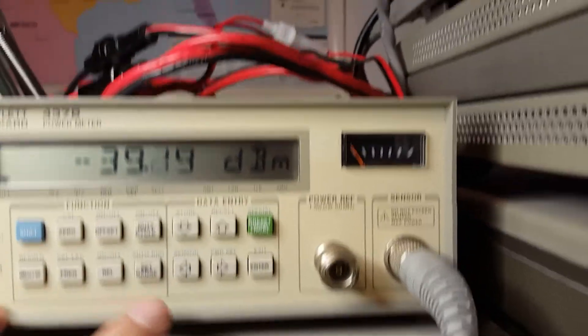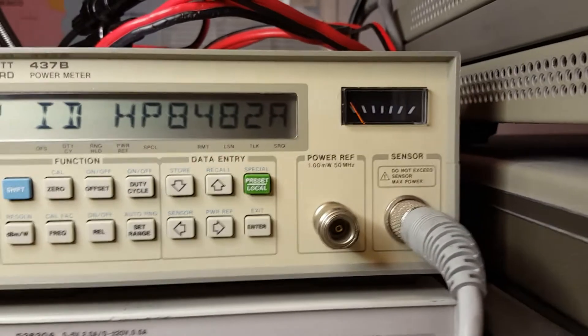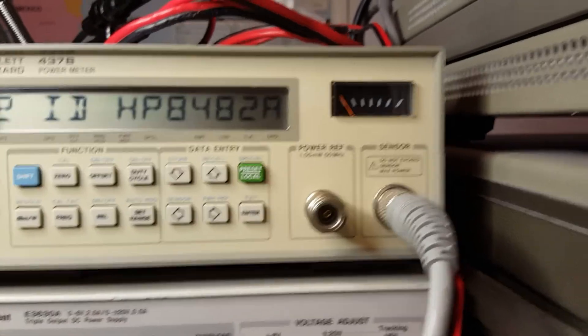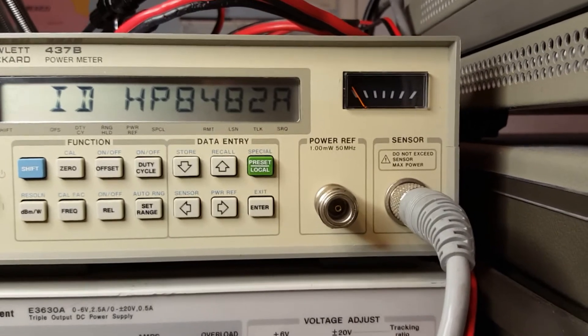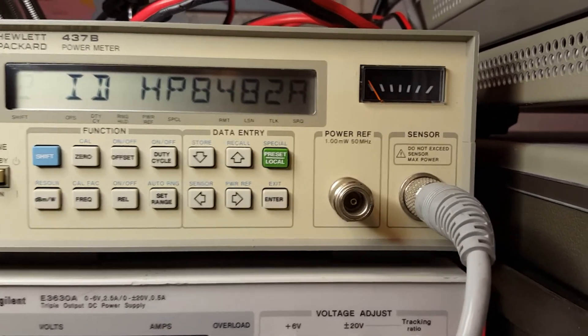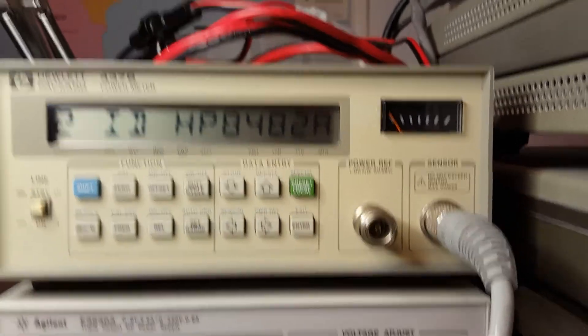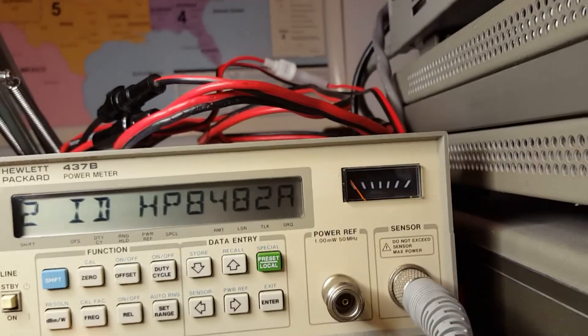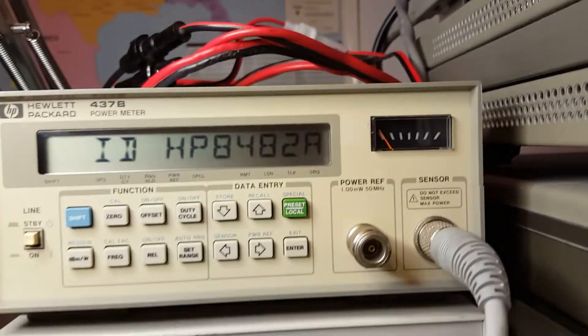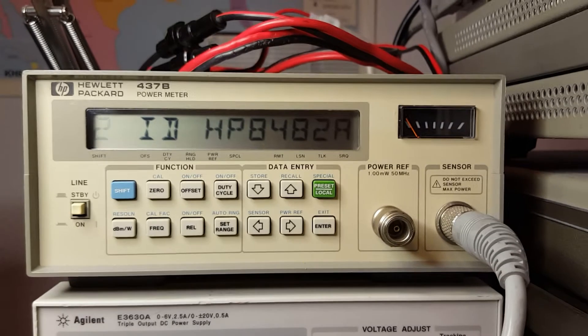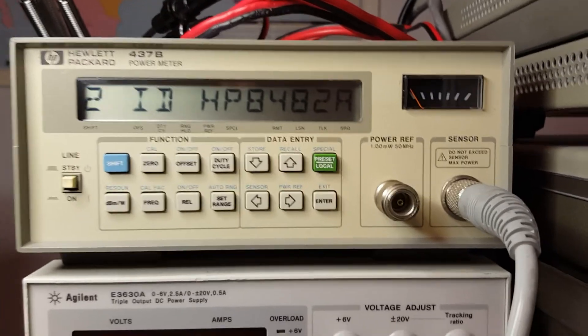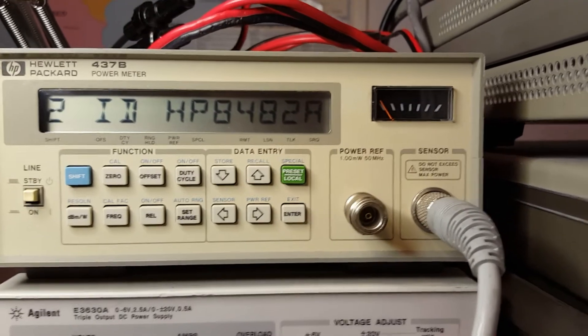However, this meter also recognizes the sensor that you connect to it. We press shift and sensor, and it's showing the very sensor we have connected. It has all of the calibration correction factors in memory. When you operate at a certain frequency, you either enter the frequency direct or the calibration factor direct, and the meter will automatically correct for the impedance variances and show you the corrected output.